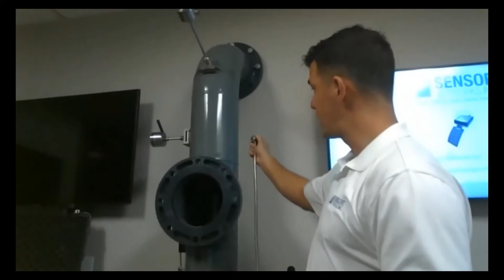When I find my spot to place the transmitter, I can either use epoxy to adhere the sensor to the pipe, or I can use a temporary putty or couplant, which is called Stopac. This is good up to about 65 degrees C. If it goes over 65 degrees, sometimes you have to replace it. Otherwise, you can epoxy them in. But it's really as simple as putting a BB of this on here. If you can see my screen, you find a spot, and you literally put the sensor down, and away it goes. So it's pretty straightforward and quick. If you want to relocate them or move them around, and you're using the different types of couplant, you can.